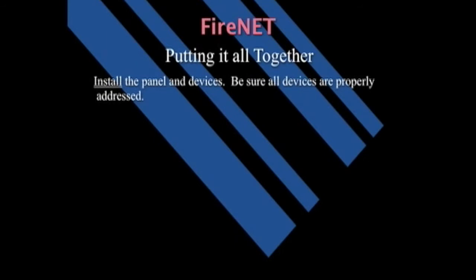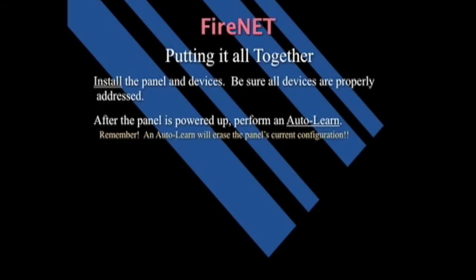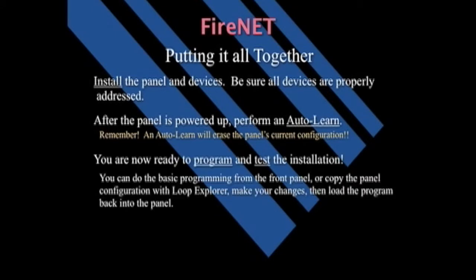Install the panel and the devices. Be sure all the devices are properly addressed. After the panel is powered up, perform an Autolearn. Remember, Autolearn will erase the panel's current configuration. You're now ready to program and test the installation.